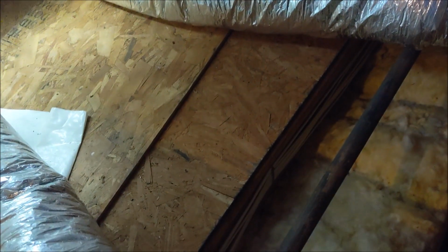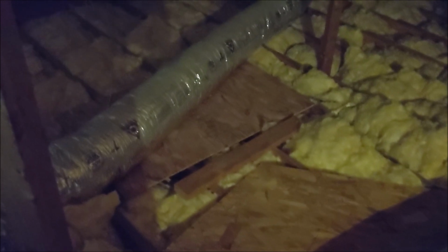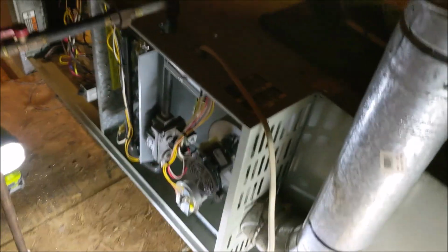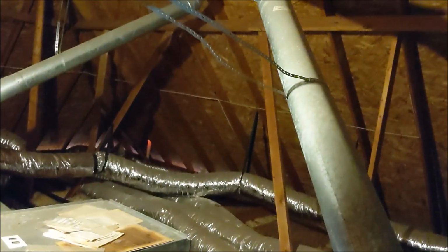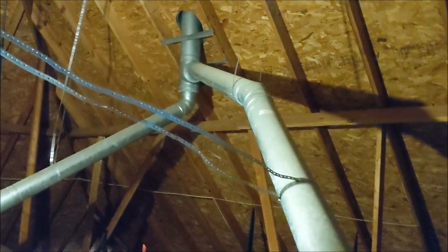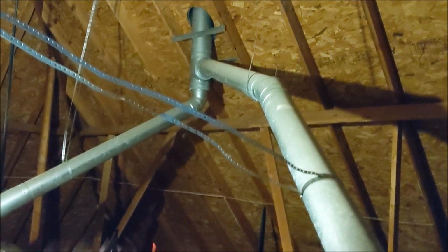See, like right there. Why? Because there's no airflow underneath them. This duct gets super cold, the attic super hot, cold follows down to the bottom, thus creating the suspected mold on the thing. If you have straps, air circulates around it the whole time, and you don't have to worry about any condensation. And they also both share the same gas furnace flue vent. It's supported, and it looks good.